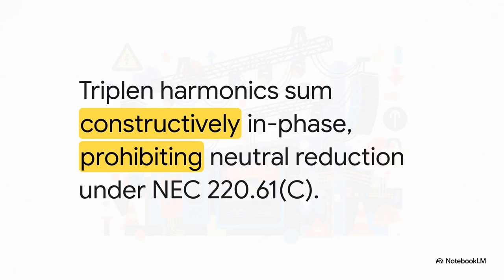They actually sum constructively, in phase, on the neutral conductor. This means your neutral wire could severely overheat even if the main power lines are perfectly balanced. That's exactly why NEC code strictly prohibits reducing the size of the neutral wire here. In fact, neutrals for these systems often have to be double-sized or run completely independently.